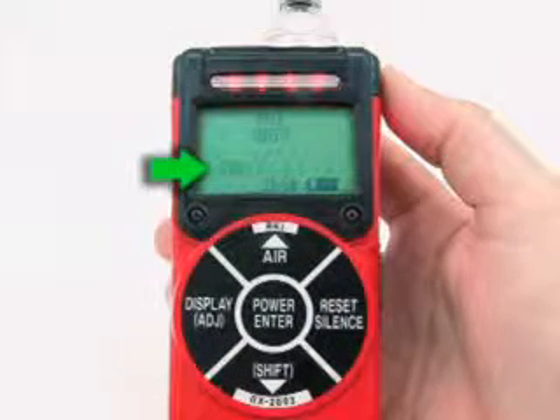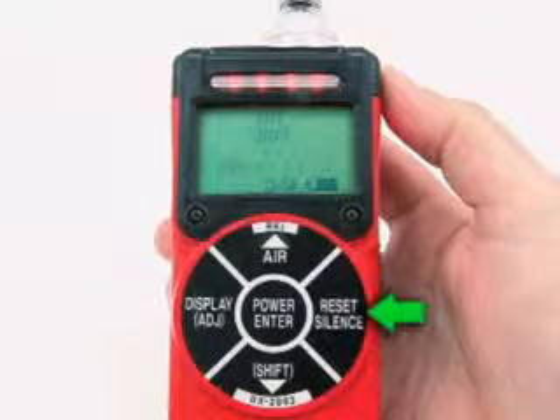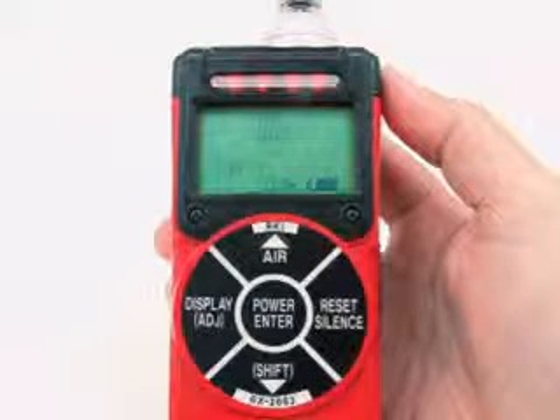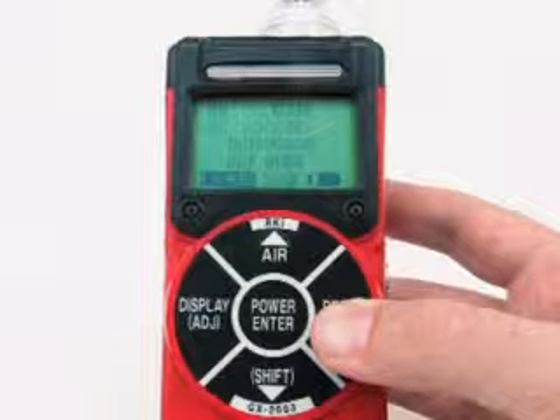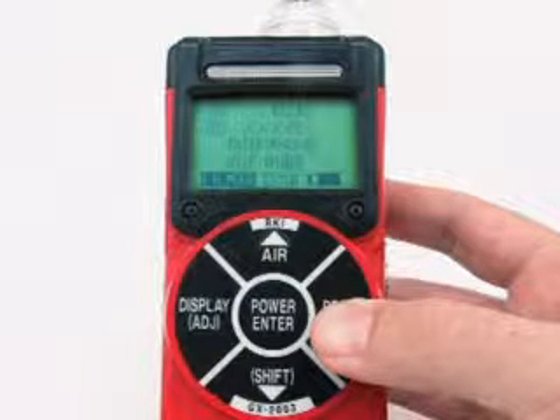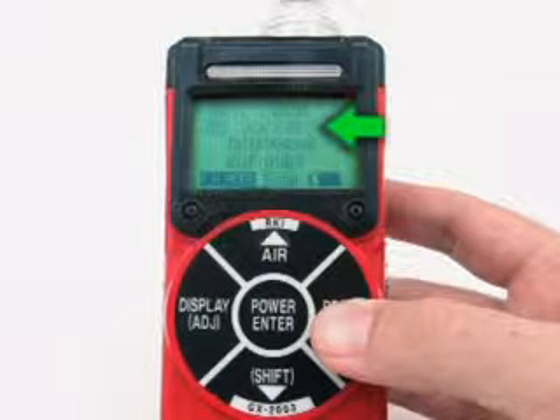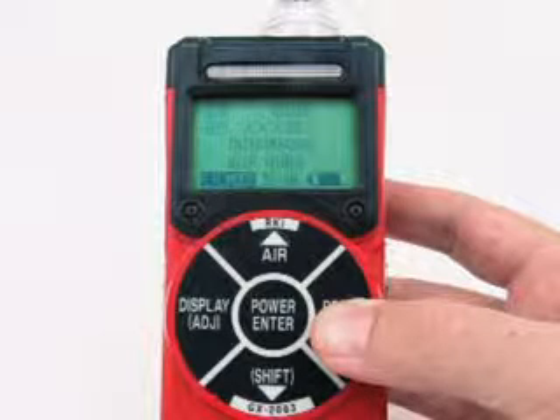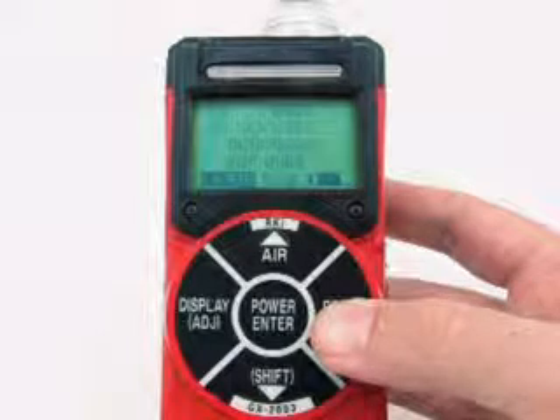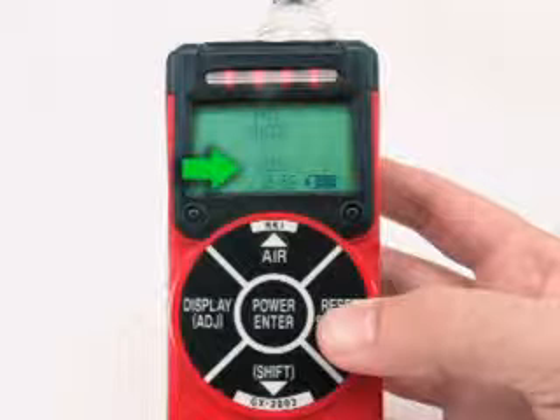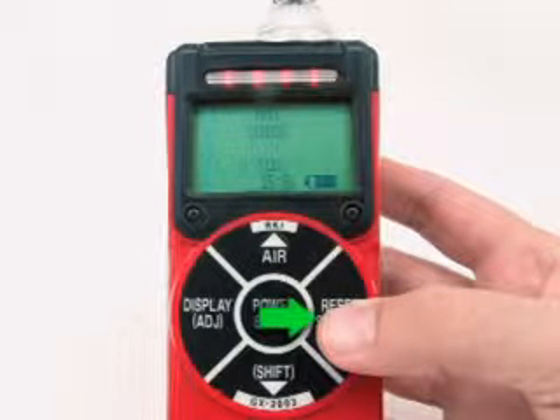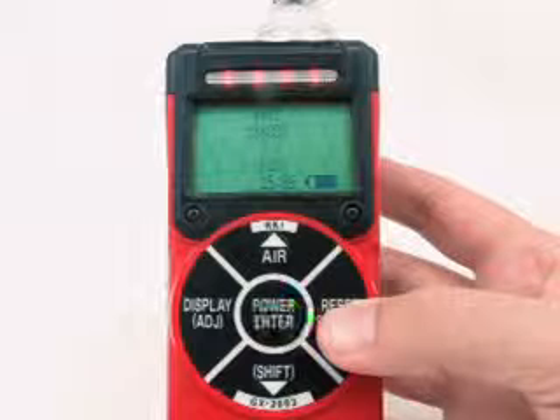If the oxygen sensor fails, press and release the Reset Silence button to acknowledge the failure and continue to bar hole mode. The gas reading for the oxygen sensor will be replaced by XXX. Replace the failed sensor as soon as possible. If the CO or H2S sensor is installed and fails, press and release the Reset Silence button to acknowledge the failure and continue to bar hole mode.